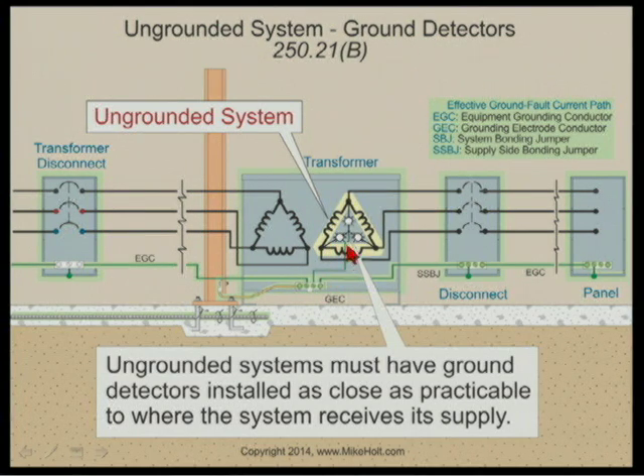Is it still an ungrounded system with the detectors in there? It's an ungrounded system. You've got to be real careful on that one because it's a very weak ground. It can't really do anything. But it is grounded because of the light bulbs. Okay, so it requires ground detectors. Now, I'm not sure if you can put light bulbs in today. They sell ground detecting devices, so that's what would be used.